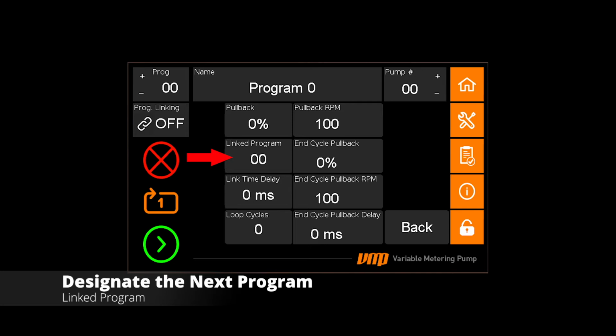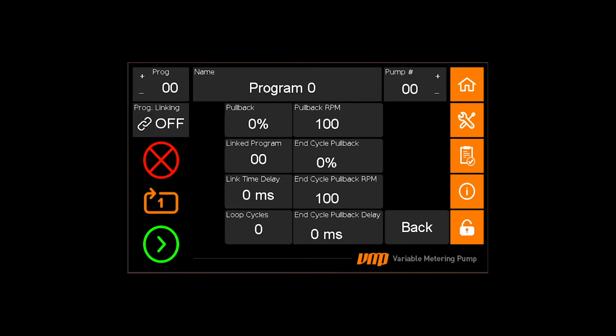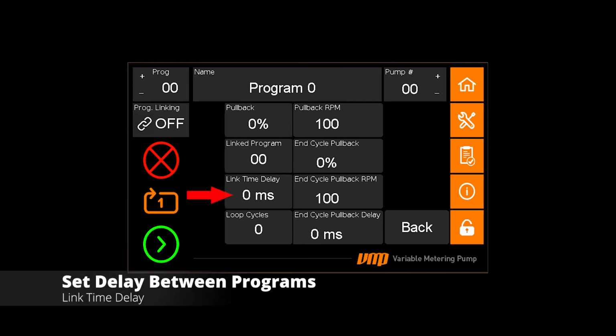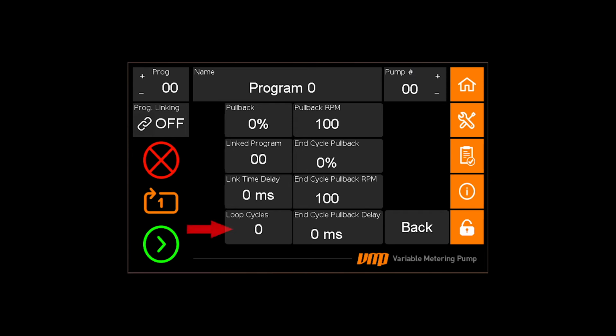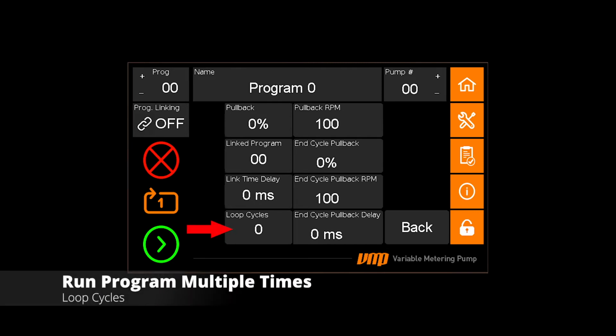A program can be linked to itself if the user wants to set a delay between dispenses or if they want to have the program loop multiple times. Under that, we have link time delay. This allows the user to set a delay between the programs or between dispenses if the program is linked to itself. Next, we have loop cycles. This allows the user to set how many times a program will run.